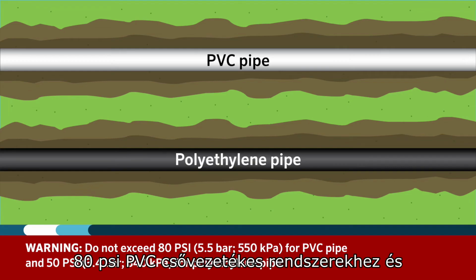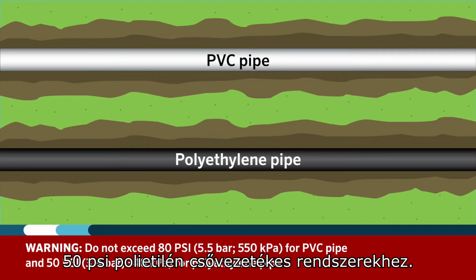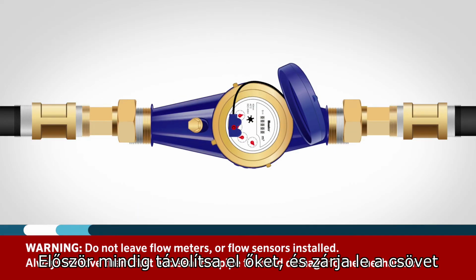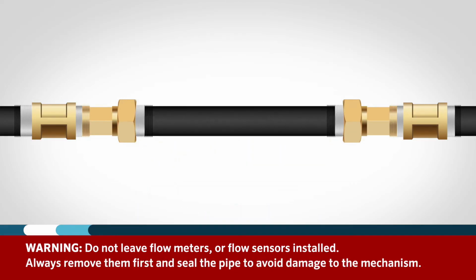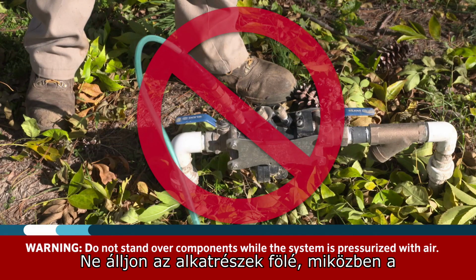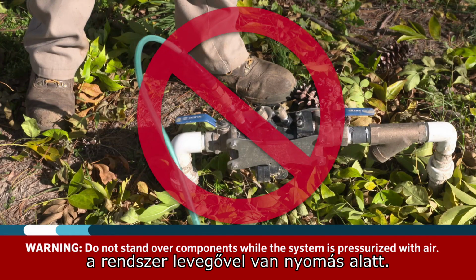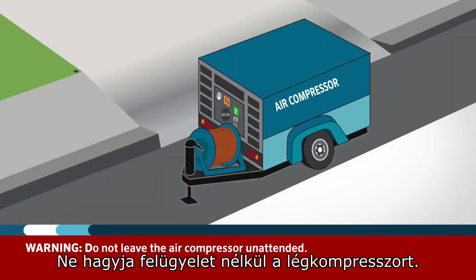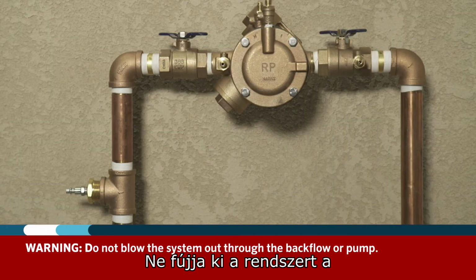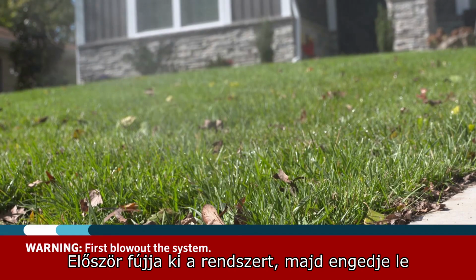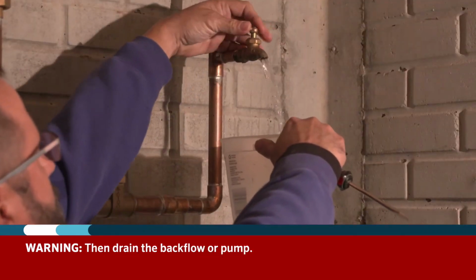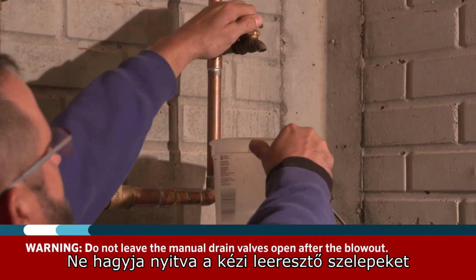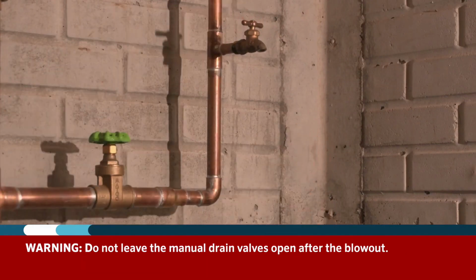Do not allow the air pressure to exceed 80 psi for systems with PVC piping, and 50 psi for systems with polyethylene piping. Do not leave flow meters or flow sensors installed. Always remove them first and seal the pipe to avoid damage to the mechanism. Do not stand over component parts while the system is pressurized with air. Do not leave the air compressor unattended. Do not blow the system out through a backflow or pump. First blow out the system, then drain the backflow or pump. Do not leave the manual drain valves open after the blowout.